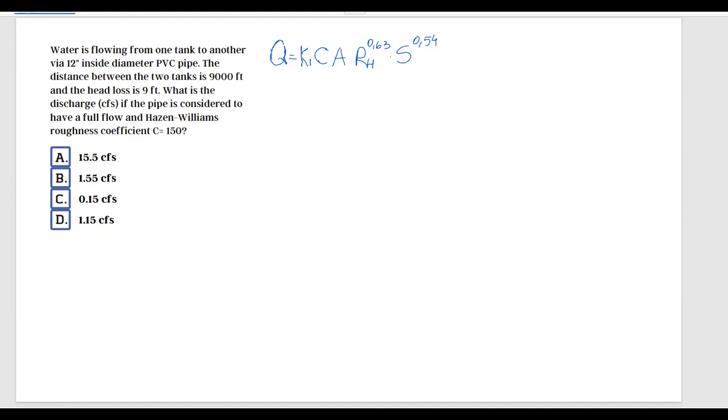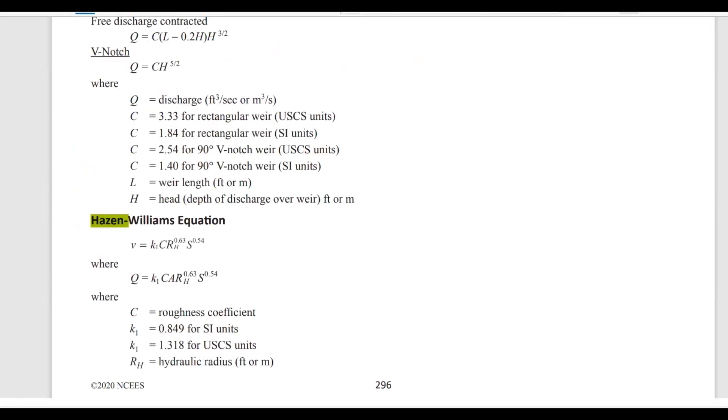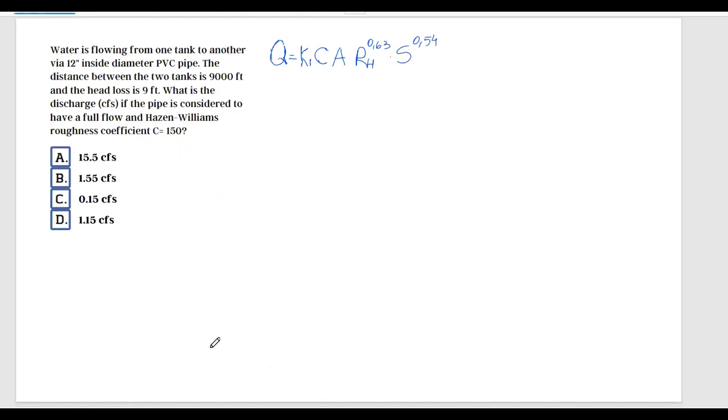We have the formula here, and now let's go over each term and see what we know and what we don't know. K1, if we go back to the FE handbook, is given here as 0.849 for SI units and 1.318 for US units. We're going to use 1.318 since the information here is in feet. So K1 is 1.318, and then we have C given in the problem as 150.